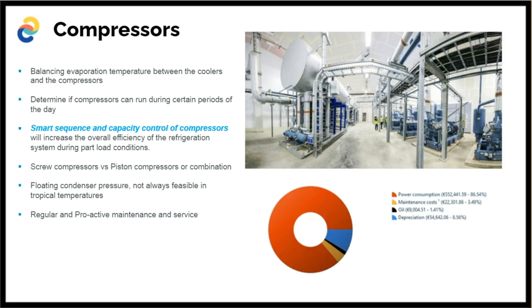And we have some nice solutions for that, and my colleague is going to talk a little bit about them, because we need to prevent compressors running in part load, because part load makes the compressors a little bit inefficient. And what are we going to select? Are we going to use screw compressors for big installations? We're looking at an installation typically between 1500 and 3000 kilowatts. Or do we need a nice combination of piston compressors and screw compressors?